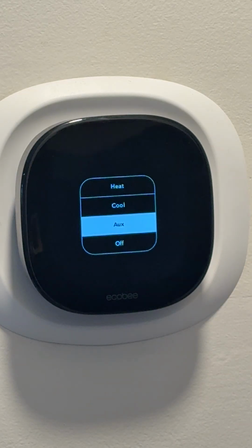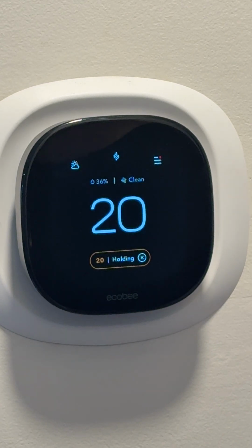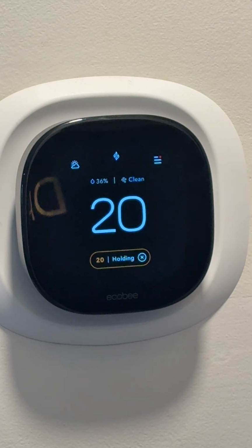This is important for hybrid customers because we might get really cold in the season. So let's say it's late December. We get a week or two where it's always below -20, so the heat pump's never turning on. We don't want it, like we have a random warm day and the heat pump decides to go on for 2 hours. We don't want that because we don't know if there's been snow accumulation, ice accumulation.